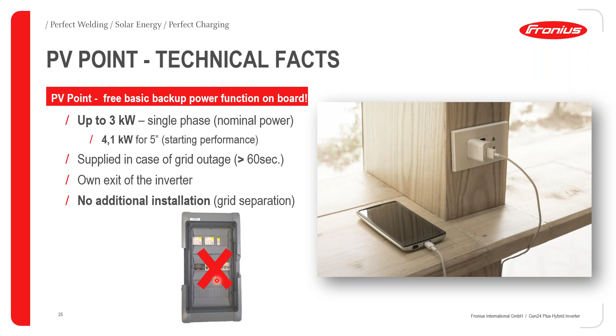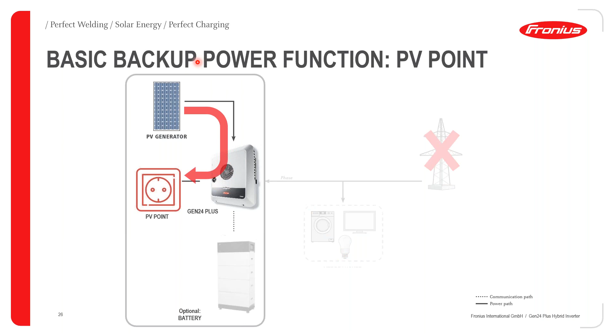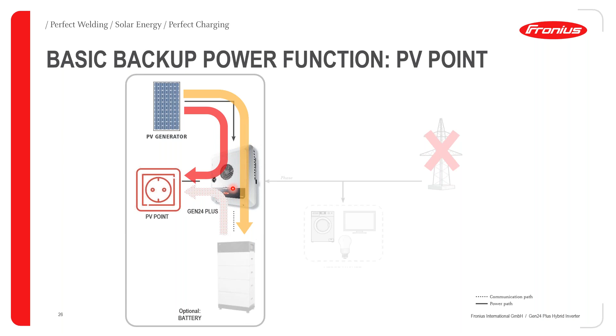So in terms of the operation of the PV Point, it works like this. If you have a grid outage, then the inverter is able to activate the PV Point, and then all the loads that are connected to the PV Point are supplied with the PV power directly, of course, after going through the inverter. At the same time, if you have a battery connected to the Gen24 Plus inverter, you can have power going to the PV Point, and then the balance of power can still be used for recharging the connected battery. In addition to that, the battery can also support the PV Point. So the PV Point can work with or without a battery connection, and that is where you also get a lot of flexibility with the Gen24 Plus inverters.